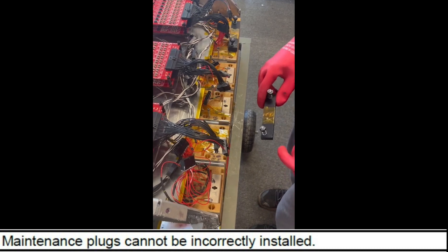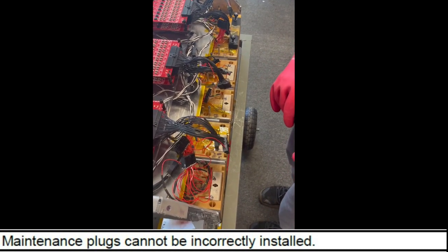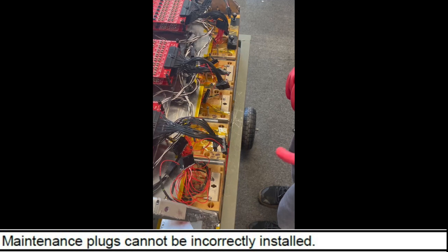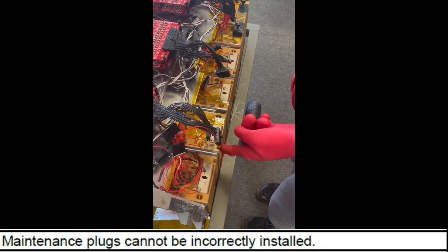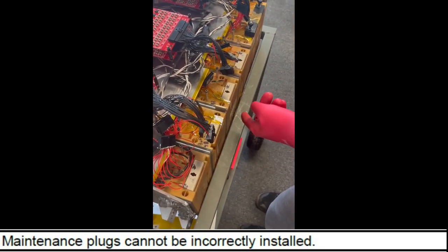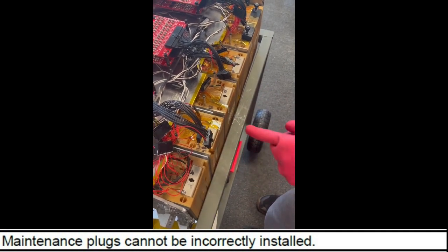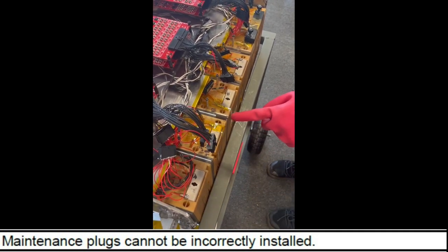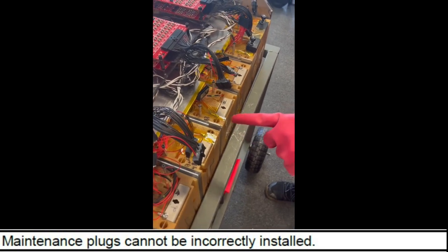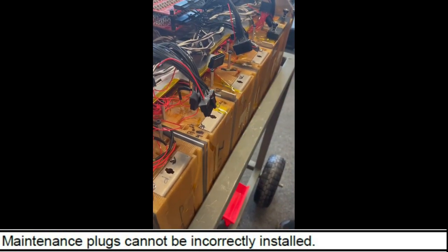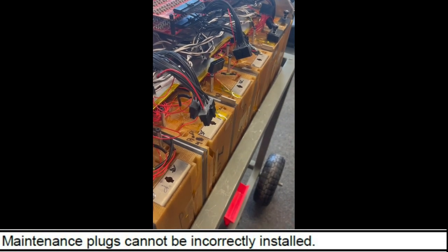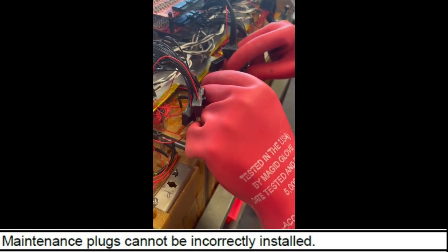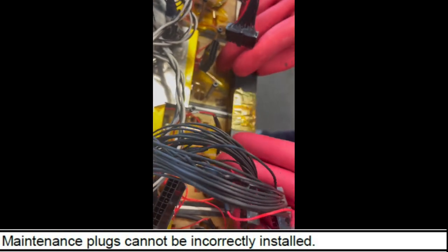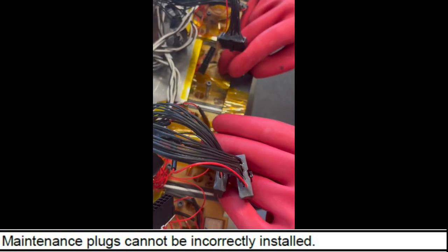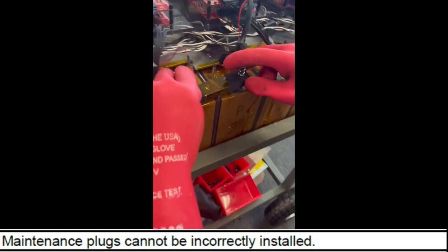In addition, our maintenance plugs cannot be incorrectly installed. This connection between the negative pole of this module and the positive pole of this module should be avoided. To do this, we structure the internal wall of our accumulator container with a raised surface such that it prevents the incorrect installation of our maintenance plugs. You can see that it is impossible to make contact with both poles at the same time.